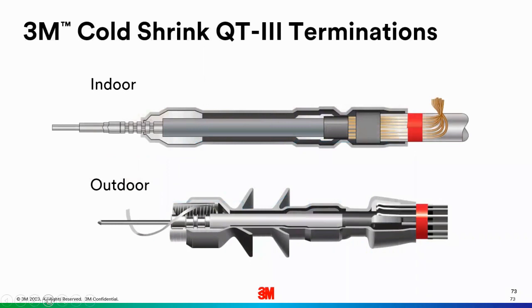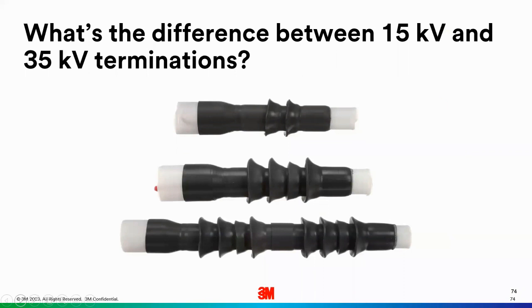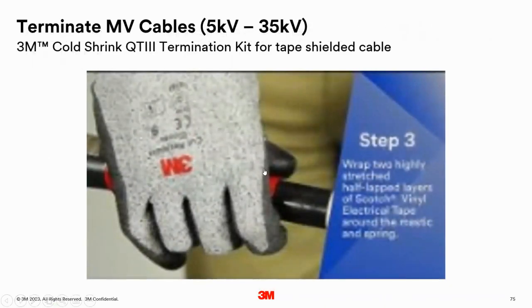And this is just a cut back from the indoor and the outdoor. You actually see right on that semicon step, there's an extra layer of high K stress mastic built into the termination that falls right on that step. I don't know if you see my mouse or not. And then we also have mastic at the end as an environmental barrier. And again, all of that is built right into our terminations. And the difference here with these outdoor terminations: 15 kV at the top, 25 kV gets 4 skirts, and typically 35 kV will get 8 skirts.